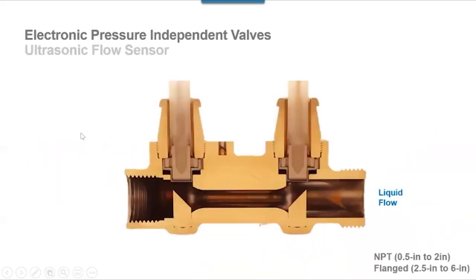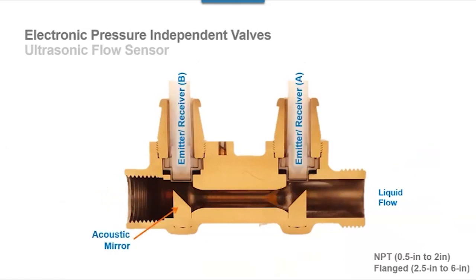Well, let's talk about the flow meter first. The flow meter is accurate to plus or minus 2% with 0.5% repeatability. The whole concept here is we have two ultrasonic transducers with the emitter receiver, and then two acoustic mirrors. There's also a temperature sensor that in our case is used in the logic to compensate for water temperature changes and to calculate and compensate for the glycol concentration. An important thing: you look at this flow meter, there are no moving parts. We design our products to be maintenance free. You don't have to go out and maintain these products.